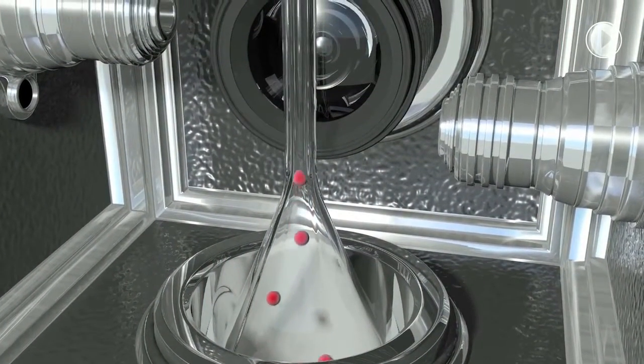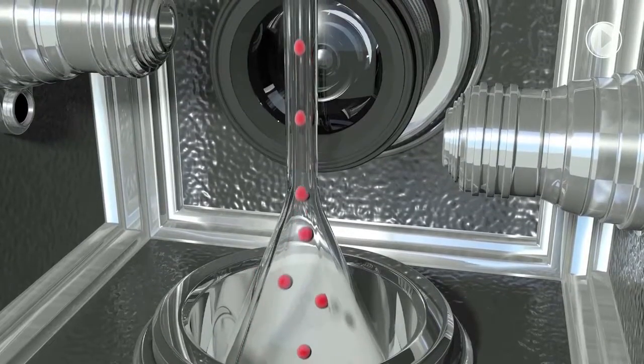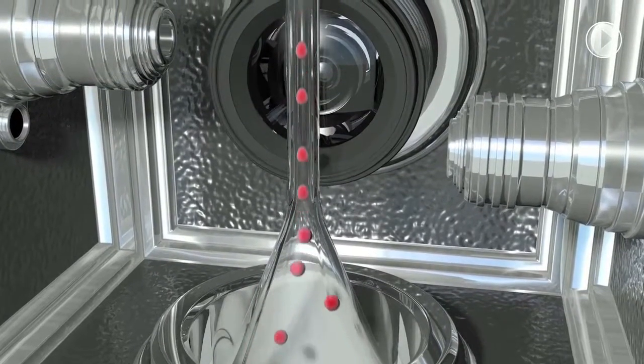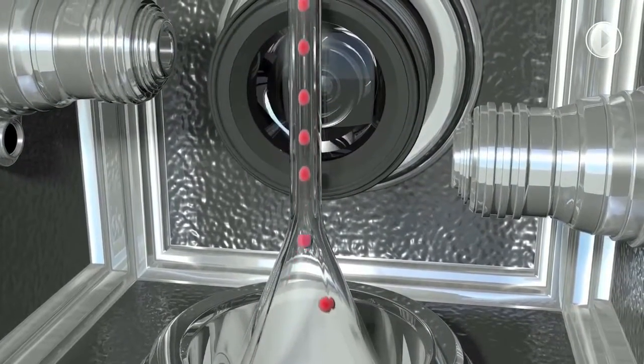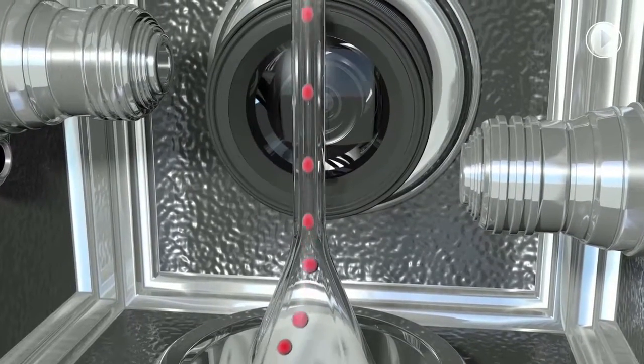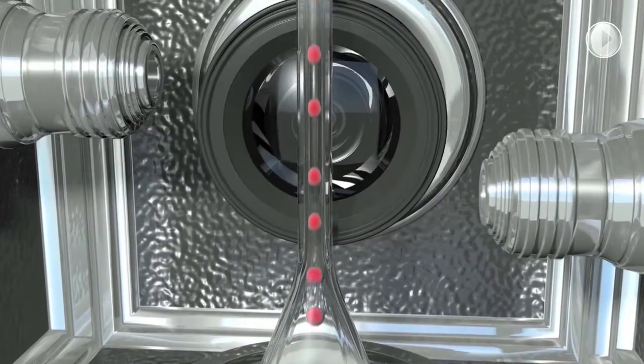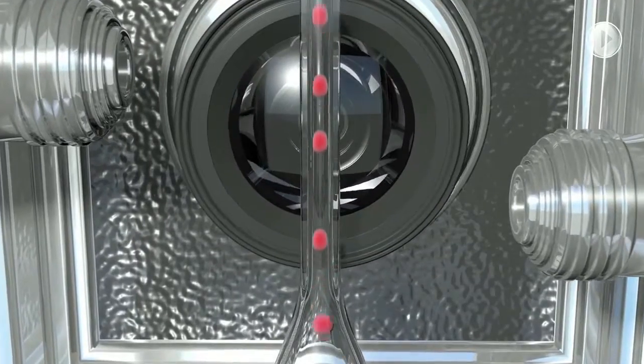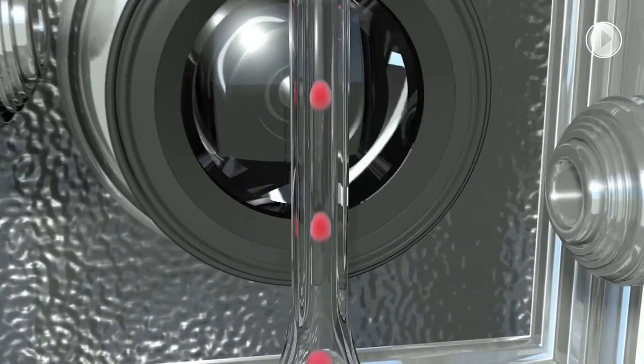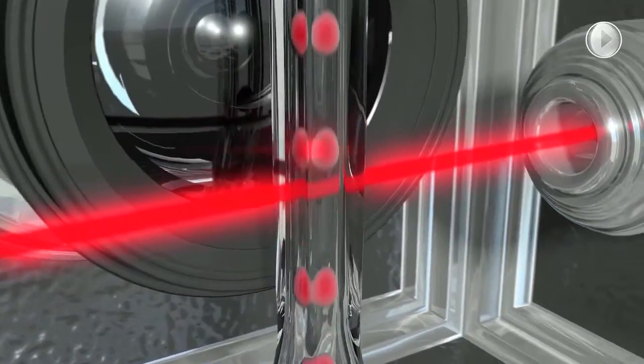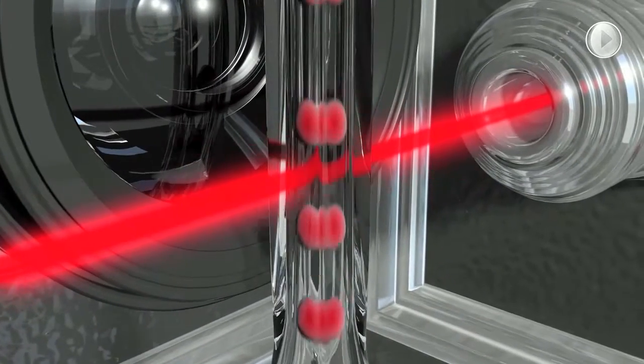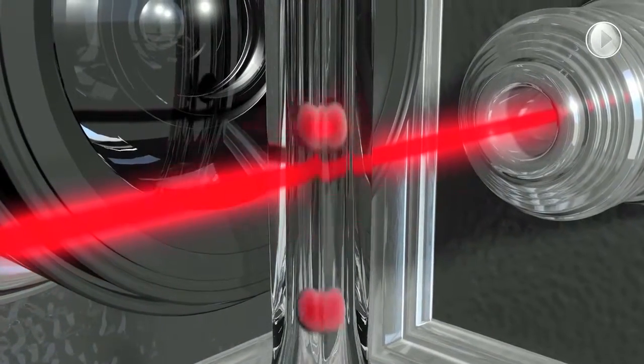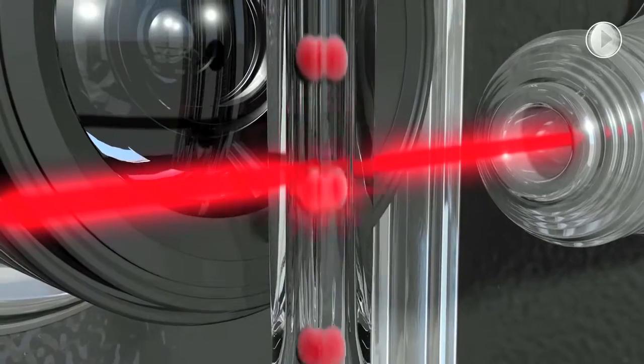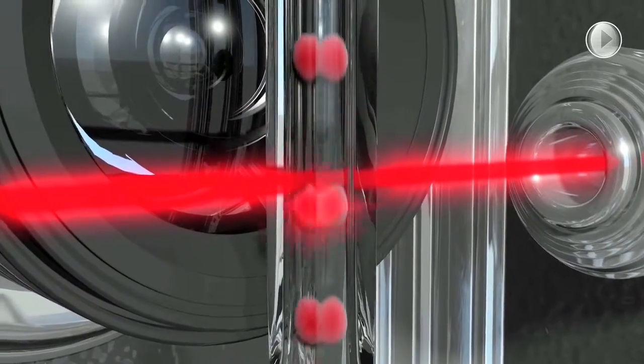A sample probe draws the suspended bead with a captured and labeled analyte into the instrument. The beads are carried by the system sheath fluid into a cuvette, where the randomly distributed beads line up in a single file. This allows the particles to be measured discretely. As each bead passes through the cuvette, a red laser excites the internal dyes, allowing proper classification of the bead, which, in turn, identifies the analyte attached to the bead.